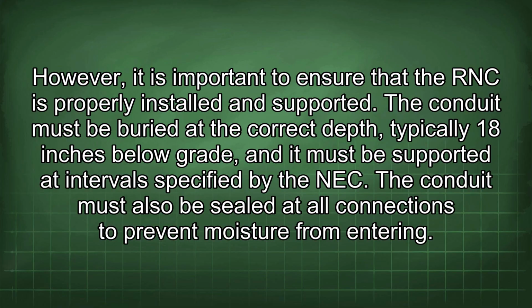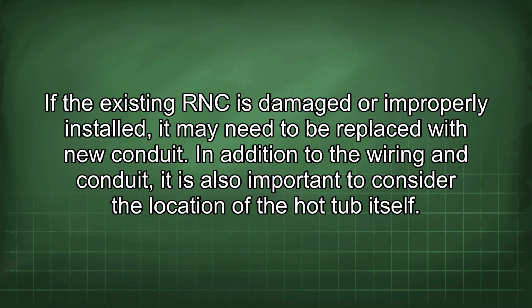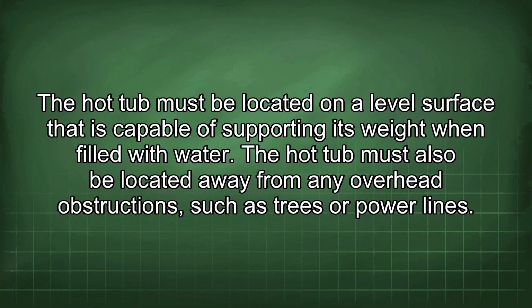The conduit must also be sealed at all connections to prevent moisture from entering. If the existing RNC is damaged or improperly installed, it may need to be replaced with new conduit. In addition to the wiring and conduit, it is also important to consider the location of the hot tub itself. The hot tub must be located on a level surface that is capable of supporting its weight when filled with water. The hot tub must also be located away from any overhead obstructions, such as trees or power lines.